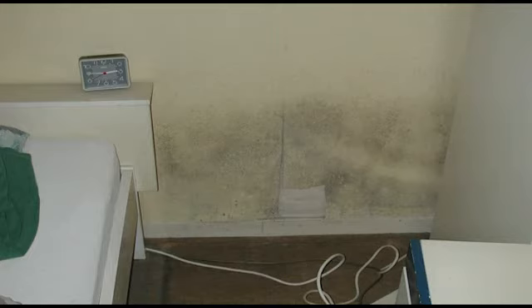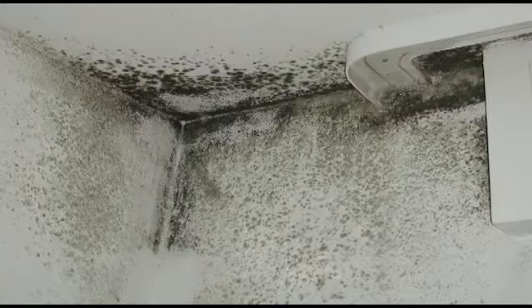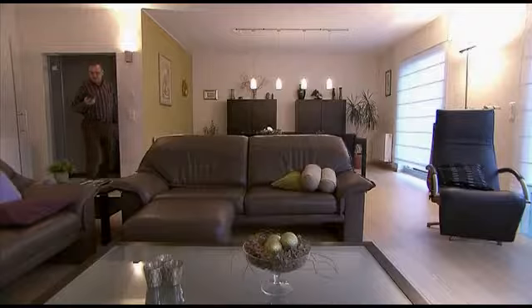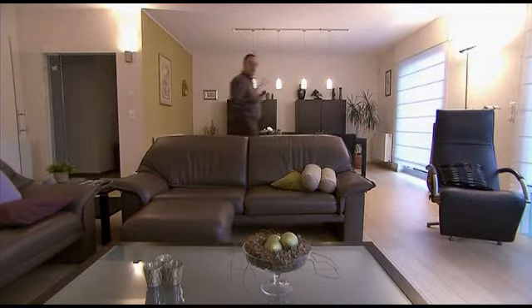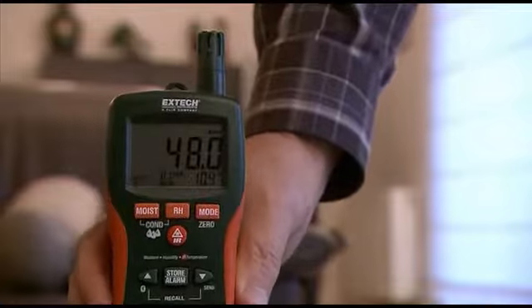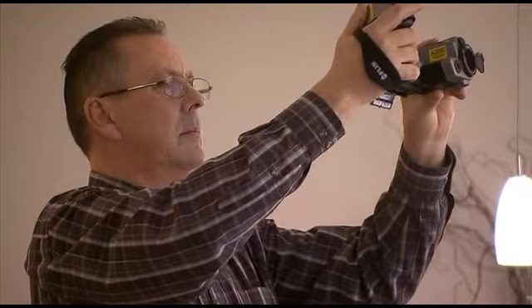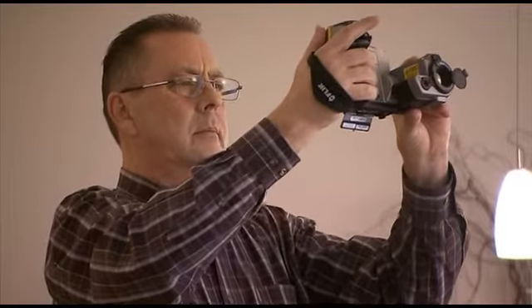One of the biggest problems in a building is the growth of mould. Not only does mould badly affect the building, but health dangers and allergies can develop in places where mould is present. With the help of an Extech moisture meter, you can easily define the relative humidity and temperature in a room. Based on these measurements, the dew point is calculated.